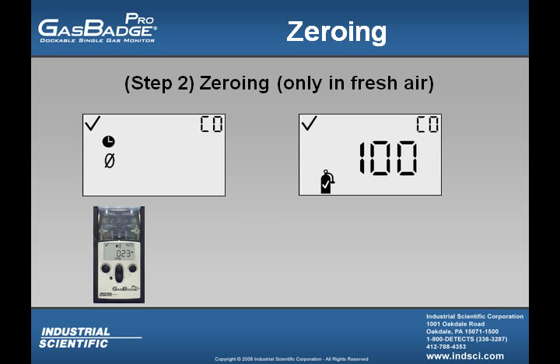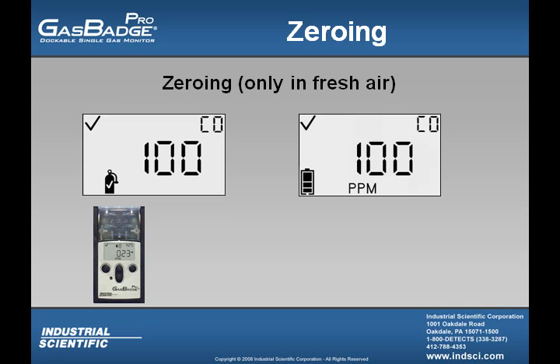After the zeroing is complete, the GasBadge Pro will emit a short beep and ask the user if they want to calibrate the instrument, showing the icon in the lower left-hand corner like that of the display on the right. The user can then wait for the GasBadge Pro to time out, or they can press the on-off button to get out of this menu. What the user doesn't want to do is press the enter button when they see the calibration gas bottle icon, because that will put them into the calibration mode.